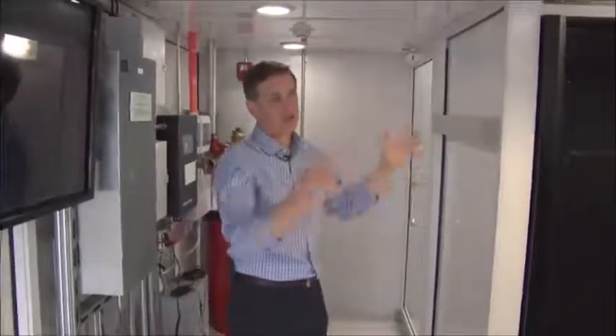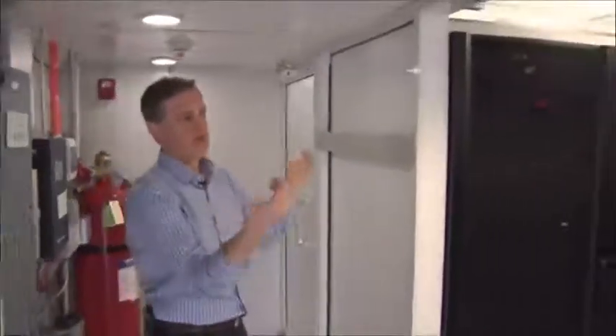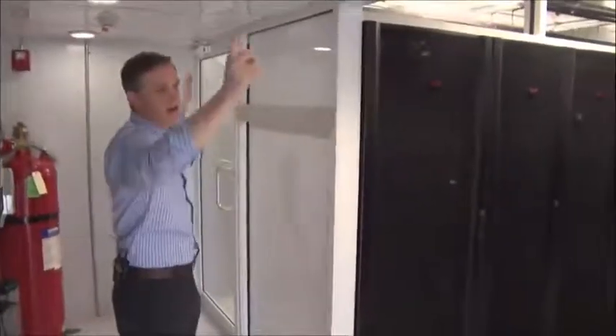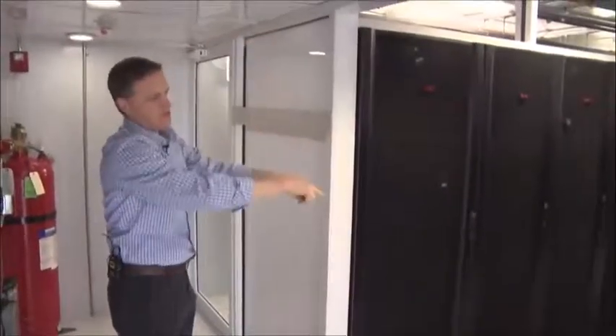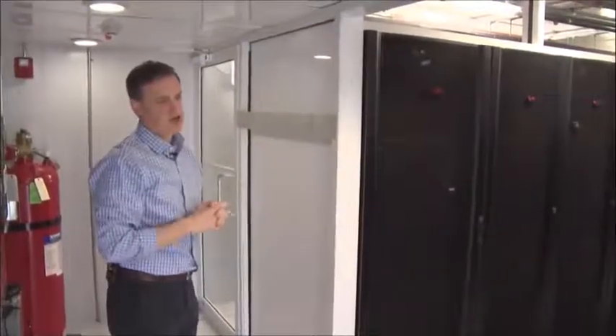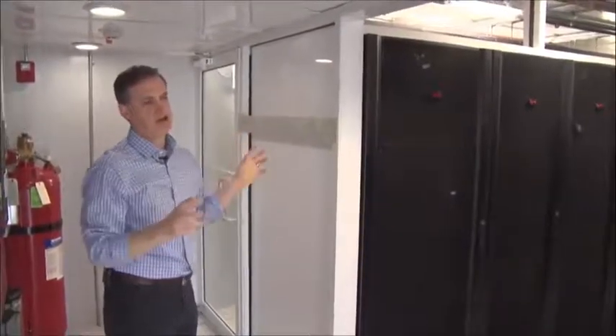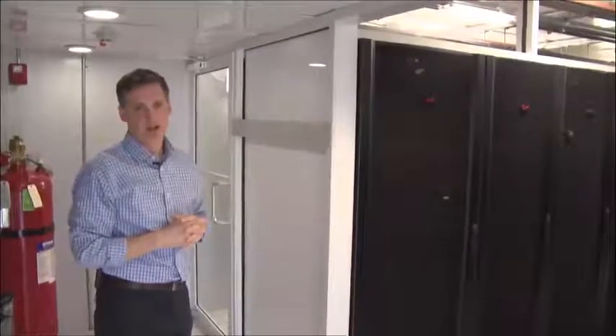As I mentioned before, we have full hot and cold aisles. This particular design happens to have the cold aisle open and in the center, but that's just one configuration. We can end up having the hot aisle here. For example, if we're doing in-row units, we might flip this configuration around, so instead of the hot aisles being on the outside, we might do it on the inside and have the cold on the outside. So we frequently change that configuration depending on the cooling system itself.